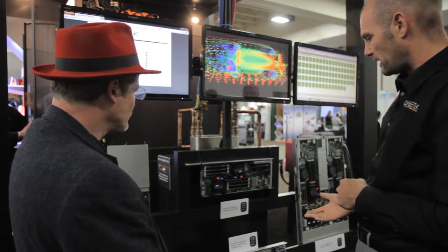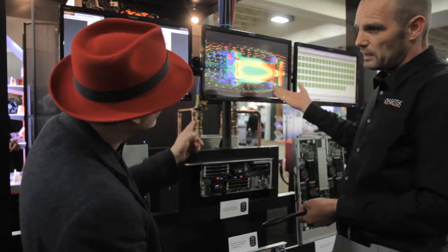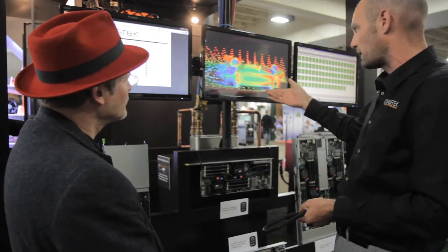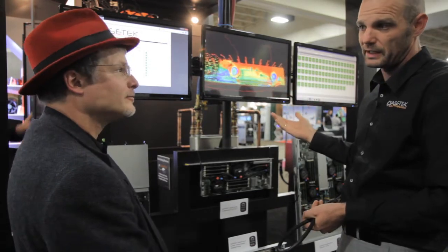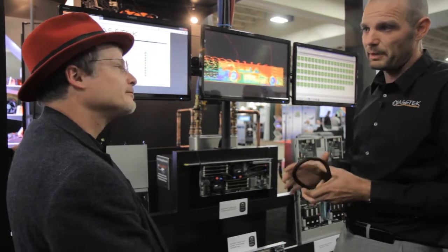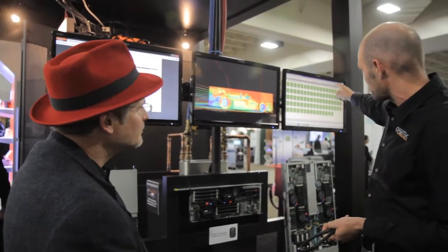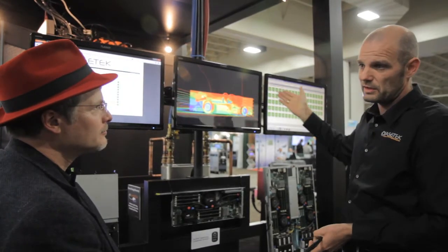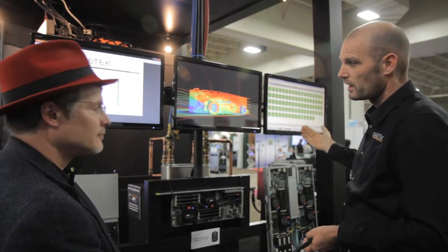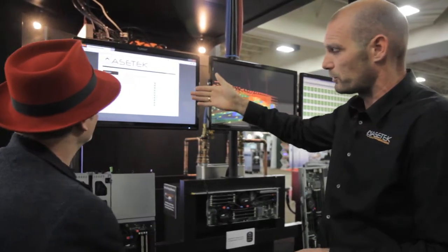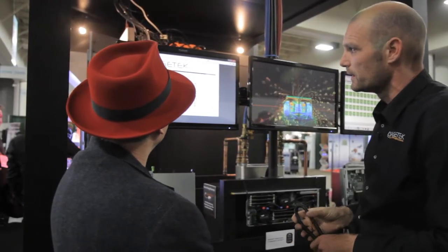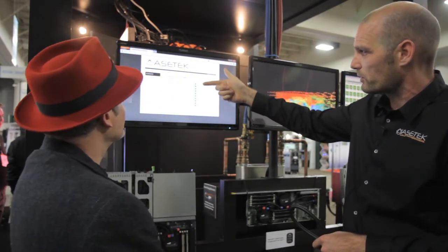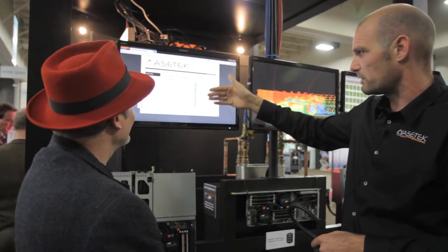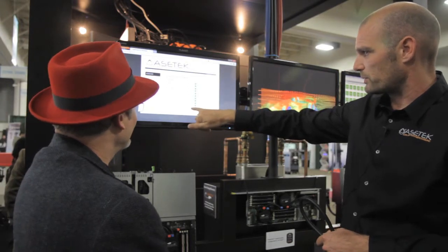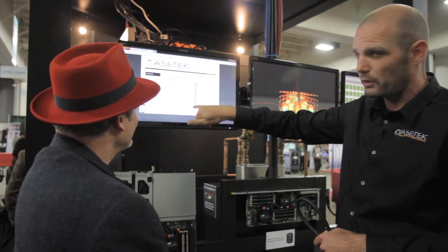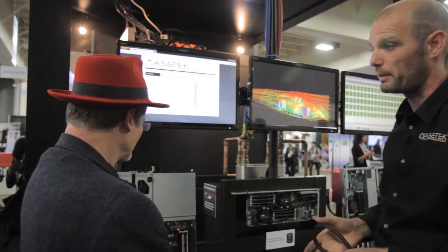To demonstrate how this works, we ran a CFD application, computational fluid dynamics, simulating a Formula car, running 90 parallel instances so every node is stressed 100%. If you look at our software surveillance system on each product, you can see the water temperature coming in and going out, liquid levels, pressures, and most interesting, we're actually removing 37 kilowatts of CPU and memory power right now.